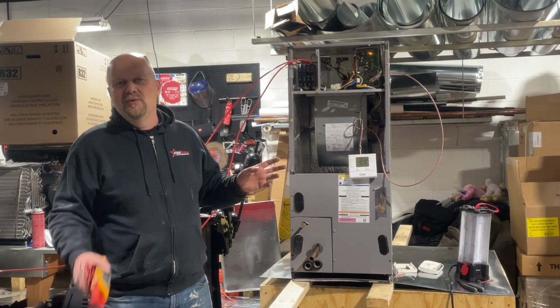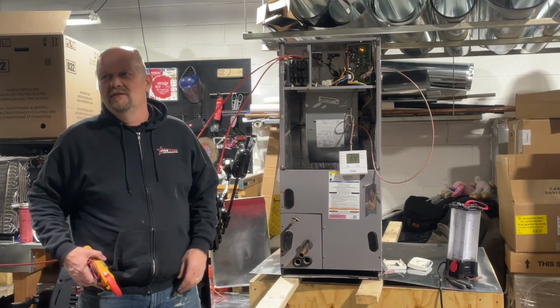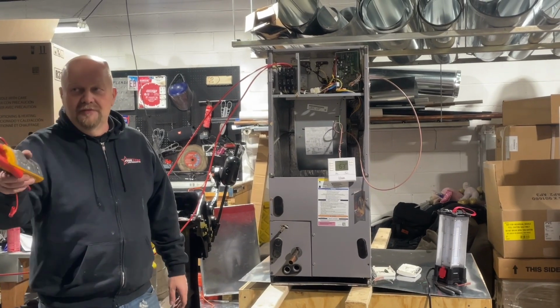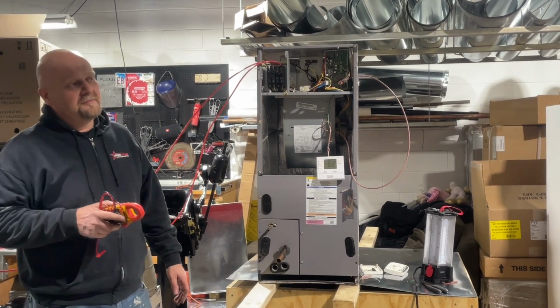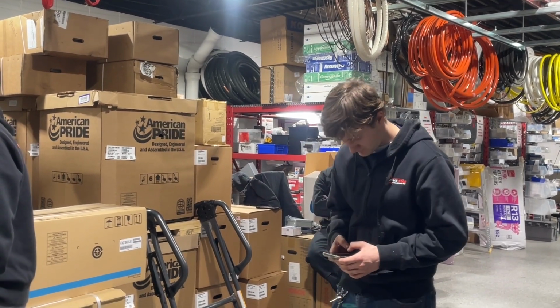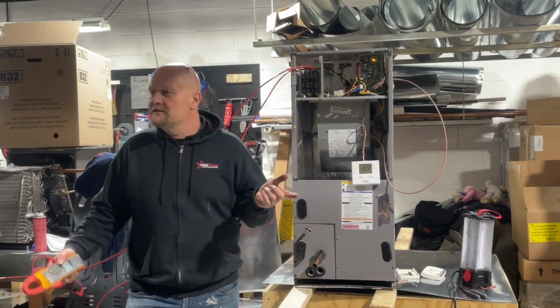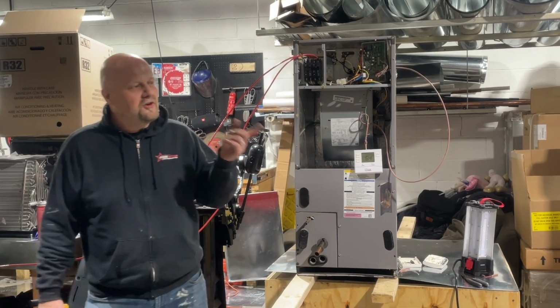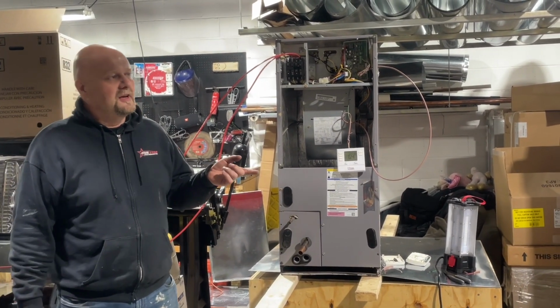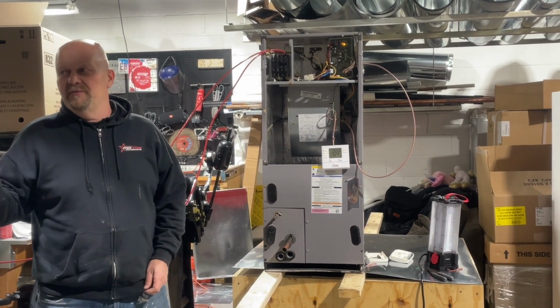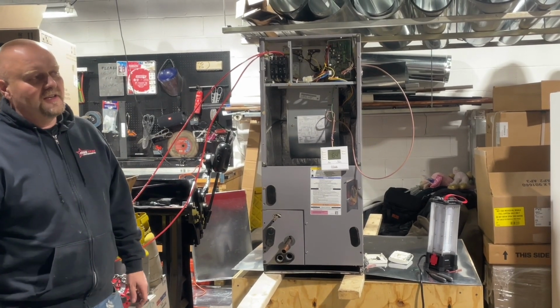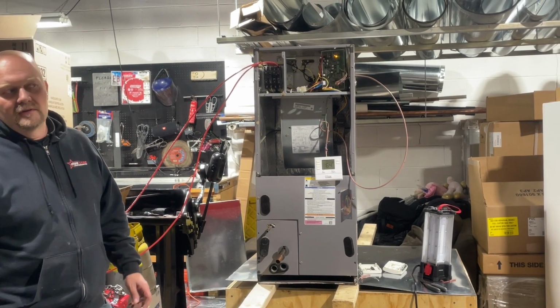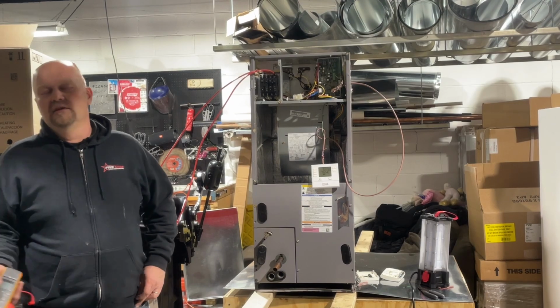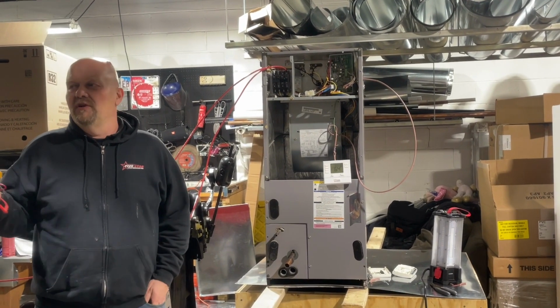Do we realistically run into these at 208? Do we run into these at 208 voltage? Eric, whip out the calculator. Let's find out how much heat we're going to get if we're sitting in a 208 high rise. Less. Quite a bit less. Let's see exactly: 40.3 times 208. Let's say about 7,000. 20% less, I'd say 7 to 8,000. Yeah, 8.3. So we lost a kilowatt.